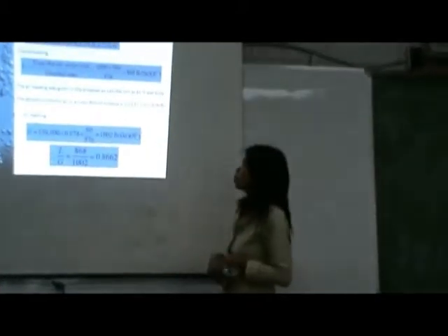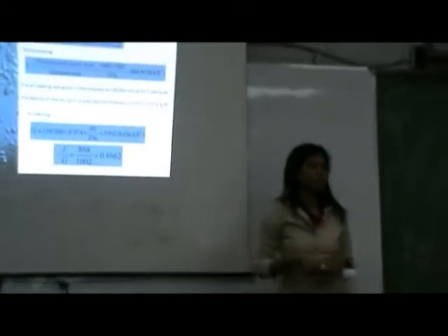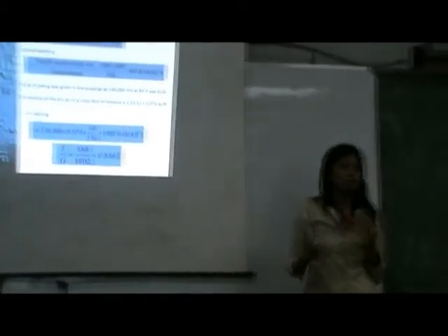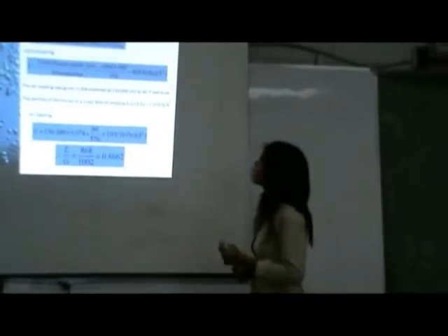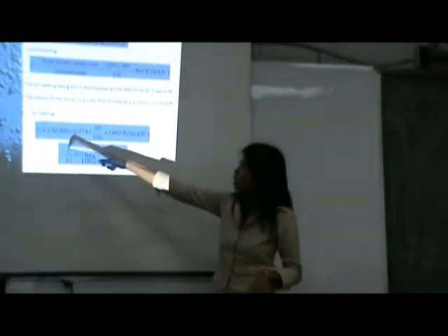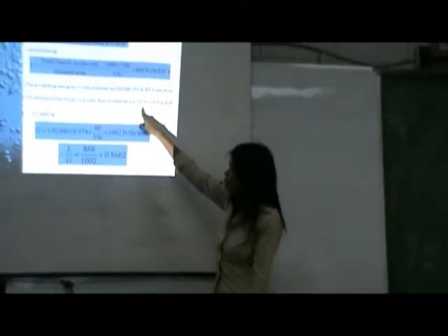Our water rate, which is given previously, is 1,000 gallons per minute, all over 576 feet squared. The 500 there is just a conversion factor to convert the unit gallons per minute to pounds per hour. Then air loading, G, is just the fan capacity multiplied by our density, which is the reciprocal of our specific volume, multiplied by our conversion factor.